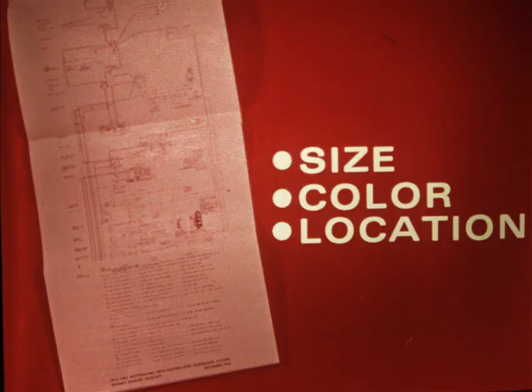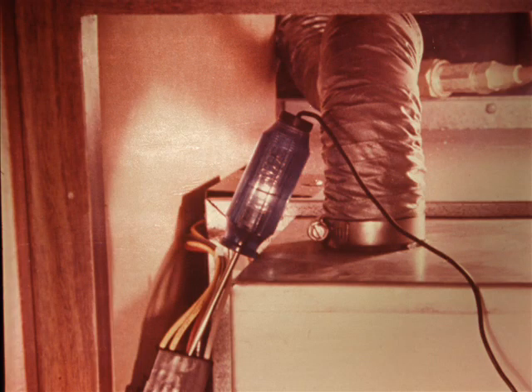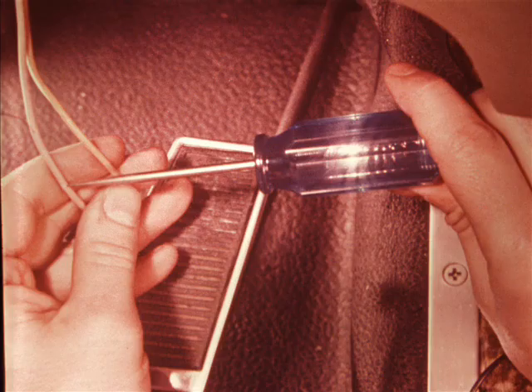Next, diagnosis of wiring problems. Don't forget that the wiring diagrams in the back of the maintenance manual identify all the wires by size and color code, and also identify connectors and their locations. In troubleshooting open or high-resistance circuits, always test for power into and out of the connector whenever possible, since many open or high-resistance conditions are at the connector rather than the result of a break in the wiring.